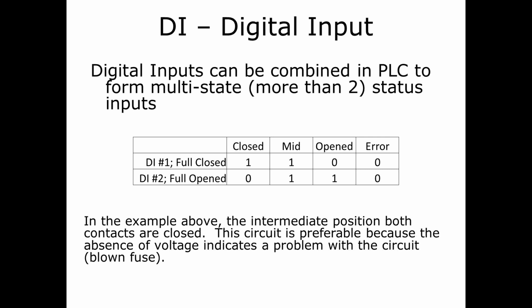And they do that because if you used one input just to show that it wasn't opened or closed, you could maybe assume that it is in transition. The problem is that if there's a problem out in the field, like a blown fuse, for example, you wouldn't know that because you're not getting an indication back. You really want to try to get indication back from the field.